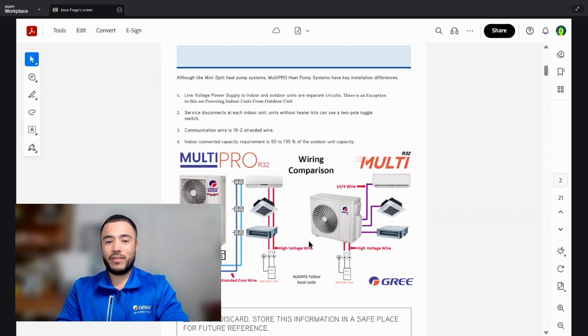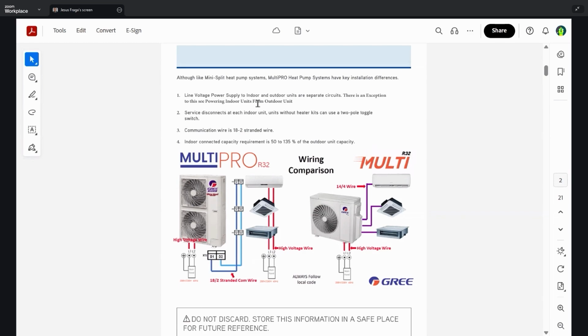And we'll see that on the next page below. To clear up some other information on this page, we recommend that you have service disconnects at each indoor unit. Those are units that do not utilize heat kits. The reason is that the amperage the heat kit will produce will not be supported by the wire that is supplied from the outdoor unit. There's an exception to this, and as I stated earlier, we'll see what I'm referencing on the next page.